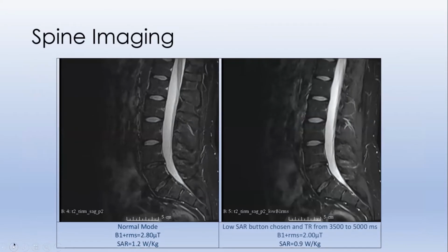So what does spine imaging look like, for instance? On the left side we have the normal mode, in this case with a SAR of 1.2 watts per kilogram. The right side is the low SAR mode, where the repetition time has been increased from 3,500 to 5,000 milliseconds, and the SAR is 0.9 watts per kilogram. Basically, there is not much difference between these two images.